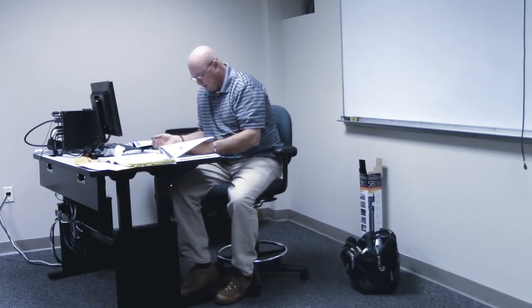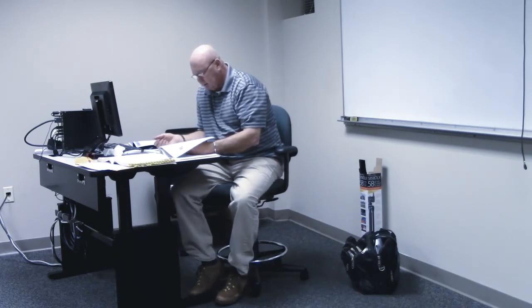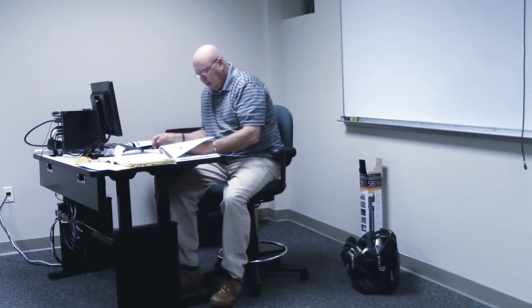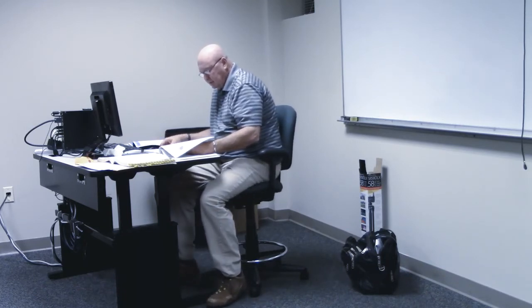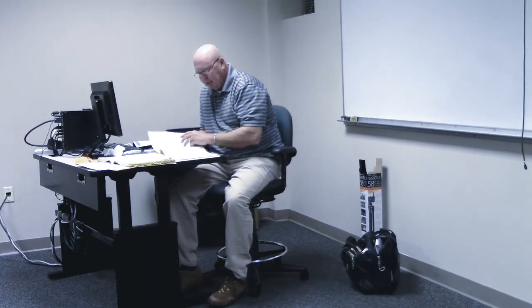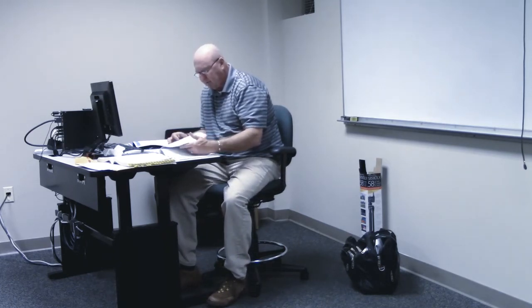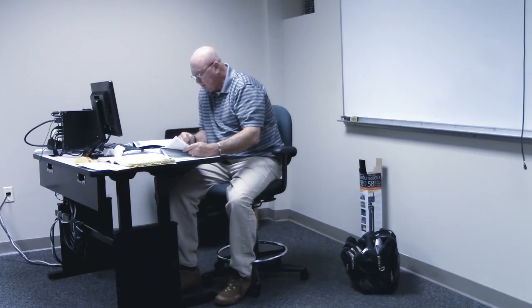NEC 517.14 applies to what? Low voltage equipment and instruments. NEC Article 490 applies to X-ray circuits and equipment over, as a matter of fact we kind of skipped over that a minute ago, but there was a reference to the voltage there on X-ray equipment, 1,000 volts. A type of non-electrified patient control device is a pull cord, an emergency pull cord. So this is usually just literally a string attached there, isn't it?